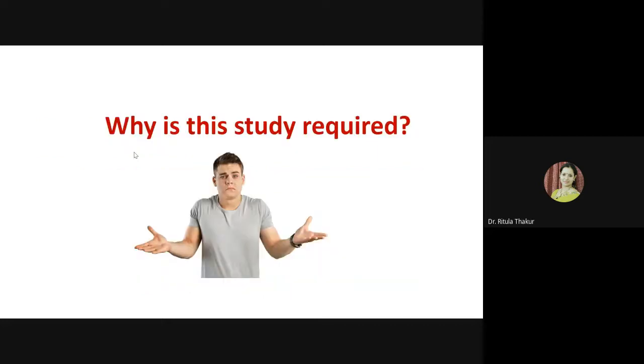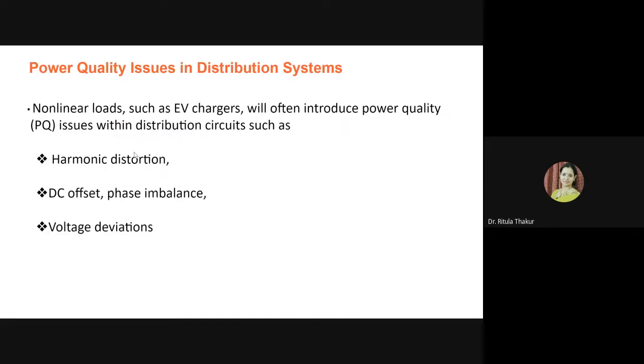Now, why is this study required? The very first question is: why do we need to discuss the effect of EVs on the distribution system? For that, we need to see this slide, which shows the various power quality issues which occur in distribution systems. We know that these EV chargers mainly consist of power electronic devices, which are non-linear loads. And those who are familiar with the term power quality know that non-linear loads often introduce power quality issues within the distribution circuits. Why distribution? Because all these charging stations are at the distribution level. The various power quality issues which mainly occur are harmonic distortion, DC offset, phase imbalance, voltage deviations, etc.